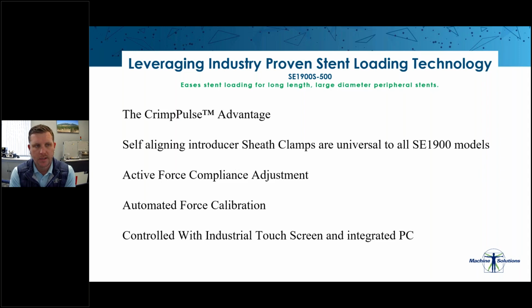The next thing we're going to talk about is the self-aligning introducer sheath clamp. And these are universal to all of our SE1900 models. The sheath clamps can easily be interchanged between all of our models, the push loading machine and the pull loading machine. The sheath clamps are designed to have a series of vertical and horizontal alignments to allow for the closed head iris to be perfectly centered inside the sheath and inside the sheath clamp for precision loading. One of the things we do recommend for loading is a flared tip on the end of the sheath as an added safety feature, and it can actually help ensure that the strut rows do not catch on the sheath during loading.